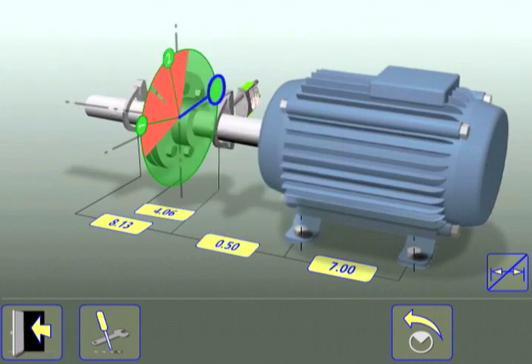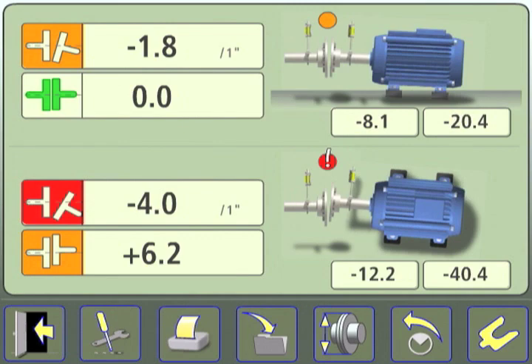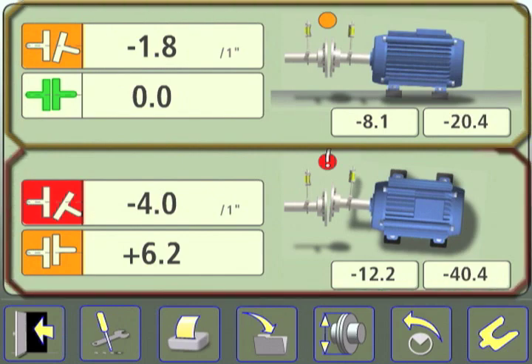Take the final reading by rotating the shafts towards three o'clock. The reading is automatically taken and the measurement results displayed. The angle, offsets, and position of the feet are presented for both vertical and horizontal views.